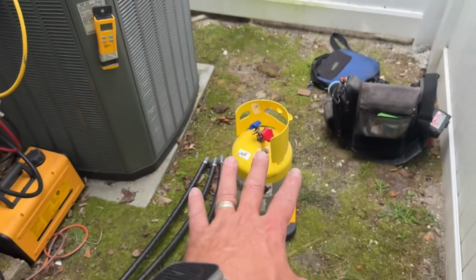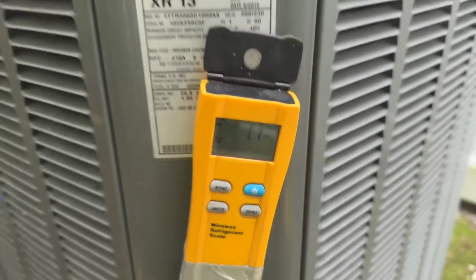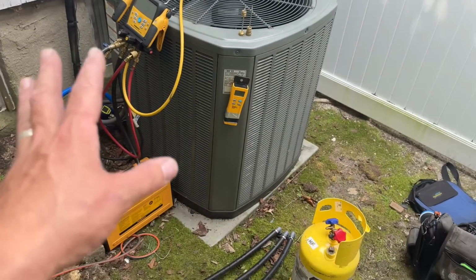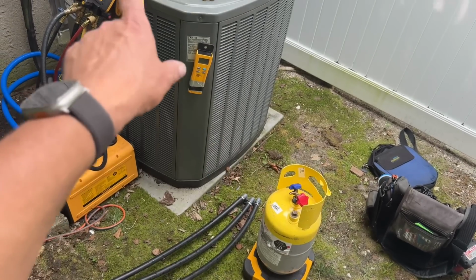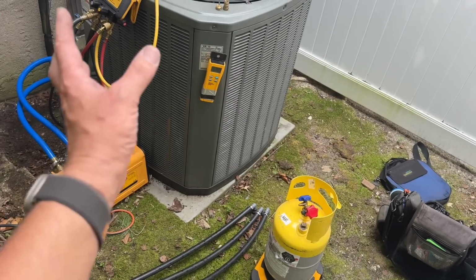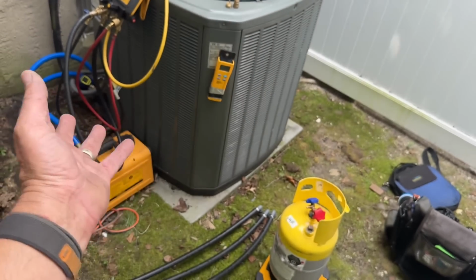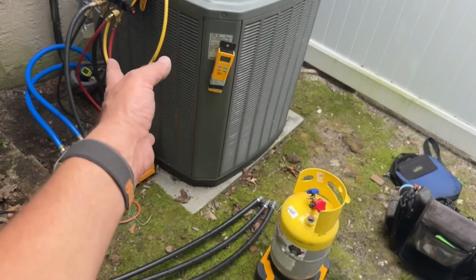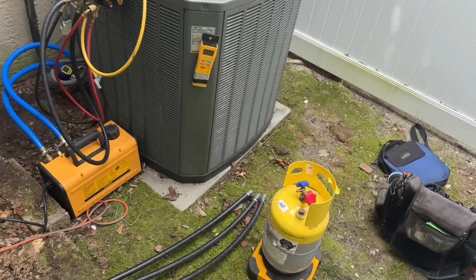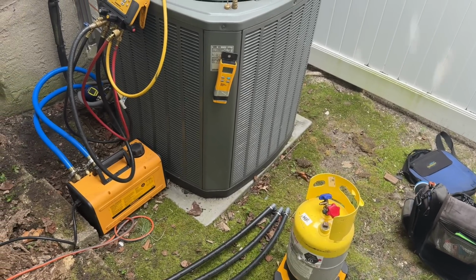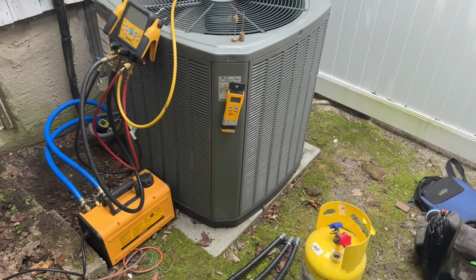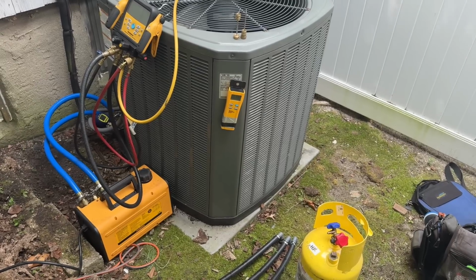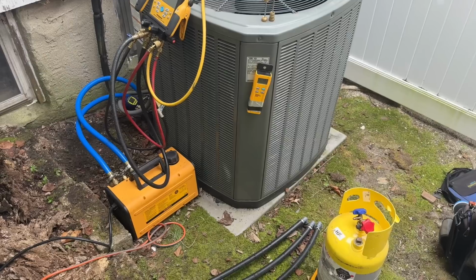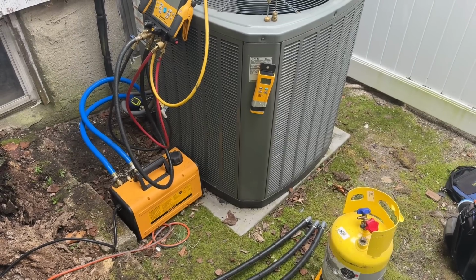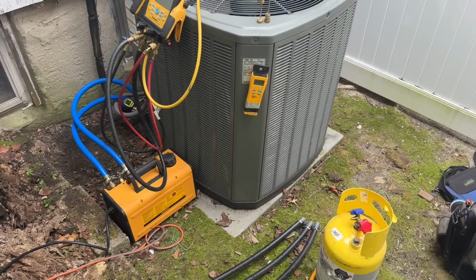So we were able to recover 1.1 pounds. Before we actually recovered anything, we had turned the system on. We were trying to pump down everything into the condensing coil. Obviously, looks like we got a lot. And then we closed both valves, and we recovered just 1.1 pounds from the line set and the evaporator coil. Not too shabby. So once we're done vacuuming down, we will open up those valves and we'll see what the pressures are like with subcooling with our brand new TXV. Hopefully this will get in there.